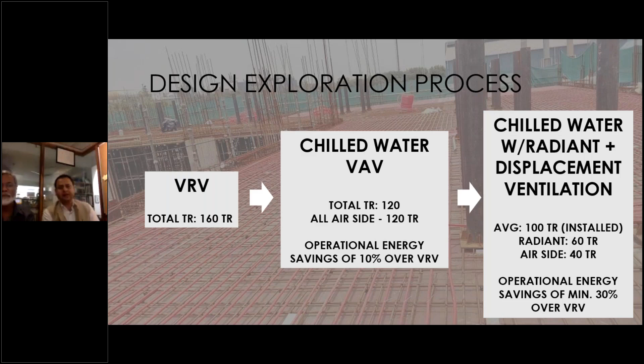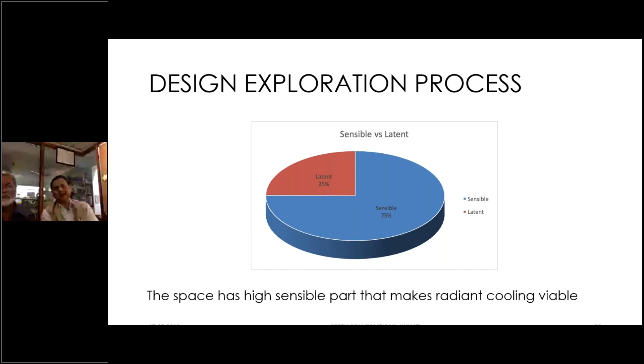So how it happens: the chilled water runs into the pipes in the slab of the radiant. The radiant pipe takes out all the sensible heat by thermal radiation and brings the temperature down. So 75% of the heat of the space is normally taken care of by this piping. The remaining 20% or 25% we normally provide with the air side. So the total air side system was only 20% as compared to the conventional chilled water or VRV system.